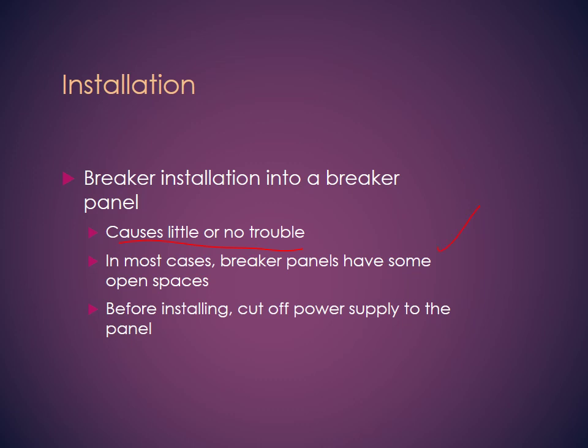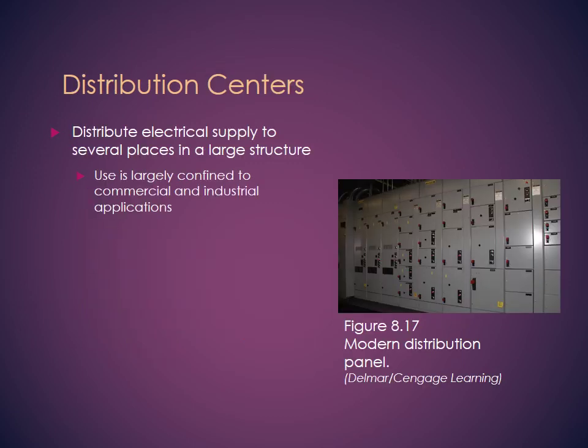There's always extra space in the panel. You hardly ever go to a panel where all the lugs or all the breakers are used. So there's always spare in case you want to add some equipment later on. Before installing anything, this is important. Before changing a breaker or installing a new breaker, you have to cut off the main power, and that's why sometimes we have a main connection to the, this is what's called a distribution center, which is a combination of all those little disconnect switches put together in a control room, because probably this is operating a big manufacturer, or also a big power plant. So you want everything to be handy, so you can go and shut off equipment if you have to, or if there's an alarm in one area.